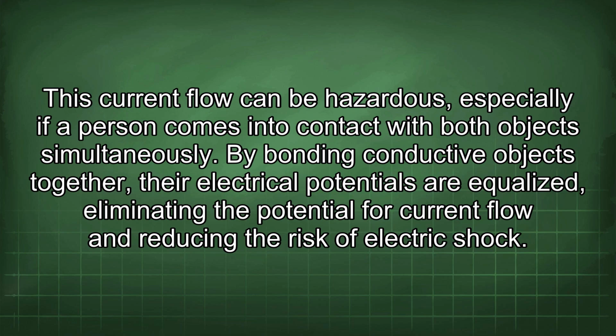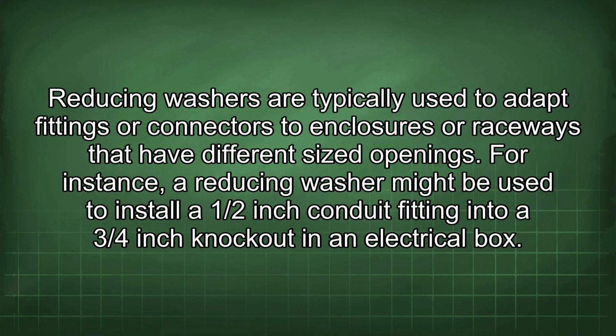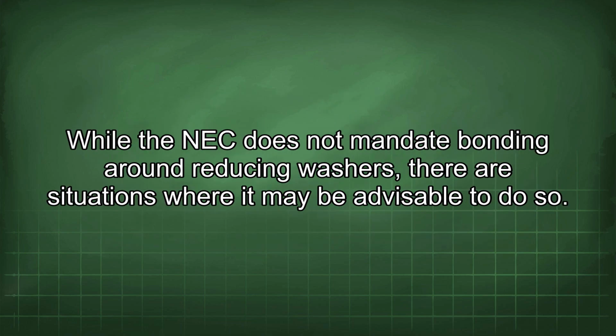of electric shock. Reducing washers are typically used to adapt fittings or connectors to enclosures or raceways that have different sized openings. For instance, a reducing washer might be used to install a 1/2-inch conduit fitting into a 3/4-inch knockout in an electrical box. While the NEC does not mandate bonding around reducing washers, there are situations where it may be advisable to do so.